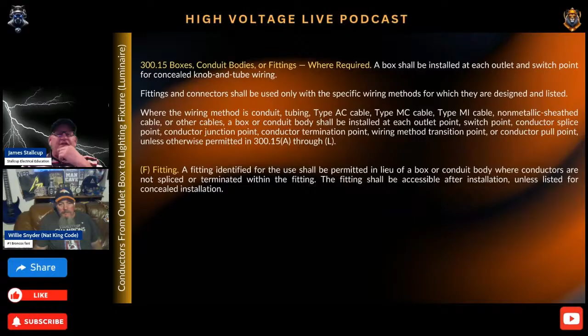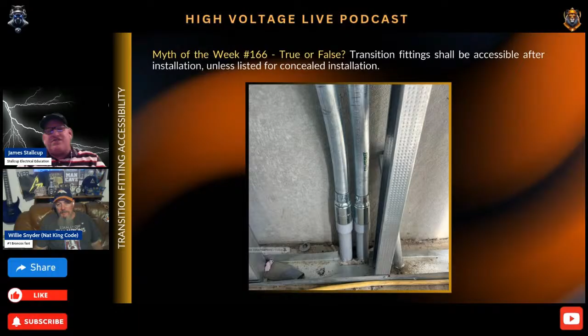If you look at the fitting, what does it say? A fitting identified for the use shall be permitted in lieu of a box or conduit body where conductors are not spliced or terminated within the fitting. And then, which is a question he asked, the fitting shall be accessible after installation unless it's listed for the concealed location. I actually saw someone mark that false, and I said you might want to look at this again, because it literally says unless listed for concealed installation. Looking at 300.15(F), it tells me no, that statement is true.